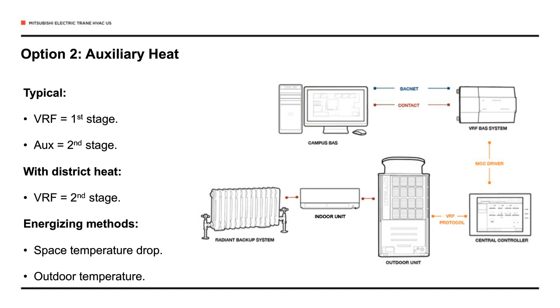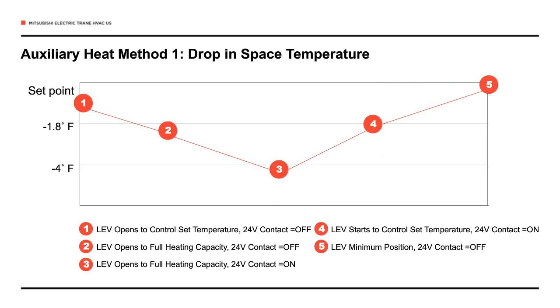If we look at the first method, we're going to do that by basically a drop in space temperature. And this is a space-by-space method. In other words, each space is operating independently. Some spaces may not even have auxiliary heat. You may only have it in critical zones in this approach. But essentially what we're doing here is, as the temperature drops, we start out at point 1 where temperature is at set point, and then it's dropping to point 2 as shown.